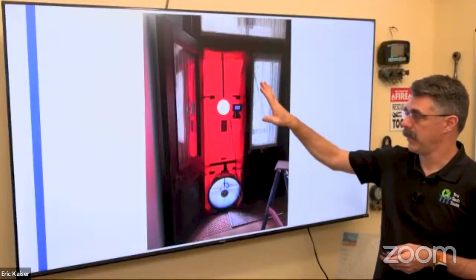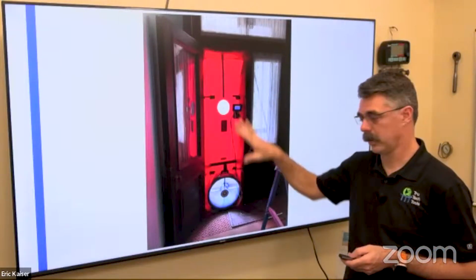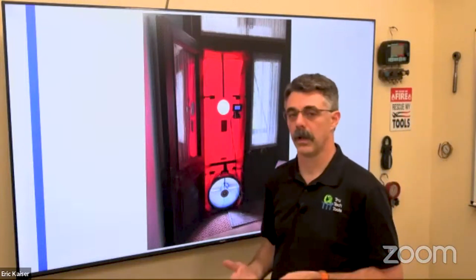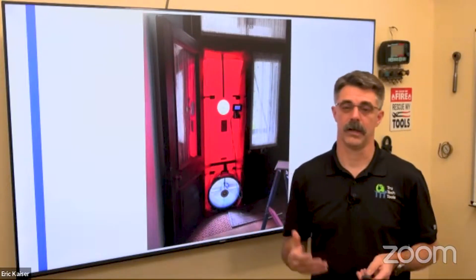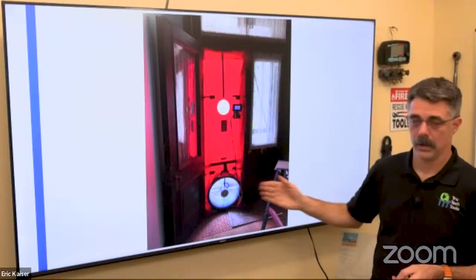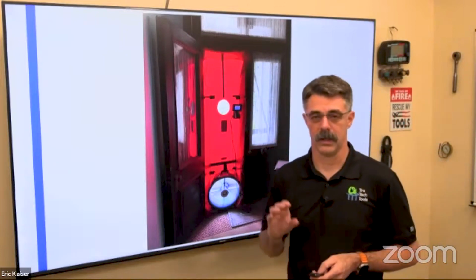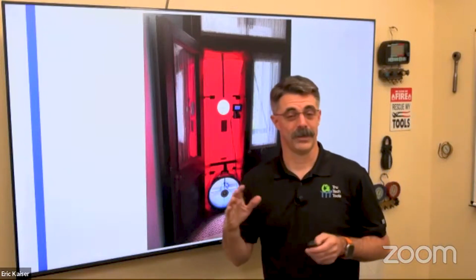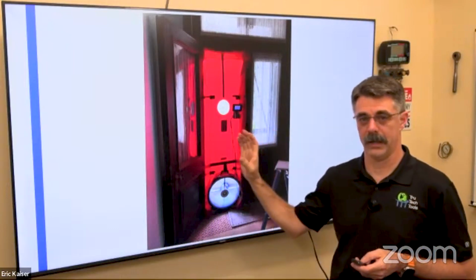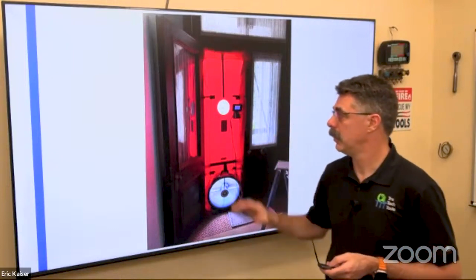But an air leakage test on the house using a tool called a blower door helps the load calculation, because then we know how much air is going to be infiltrating into that house. We understand that. Otherwise, we're making a guess. And if we're not testing, we're guessing. So a house leakage test is a really good idea to help dial in that Manual J. Does it have to be done? No. There are guesses. There are options in Manual J that you can put in there as standard options without doing that test. But if you really want to try to dial it in, it's a great idea to do that test.